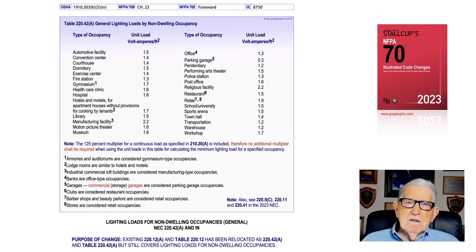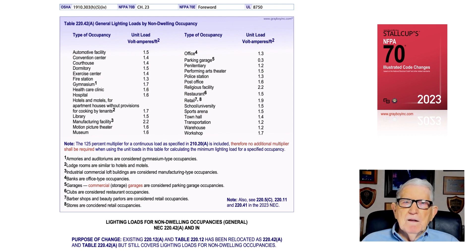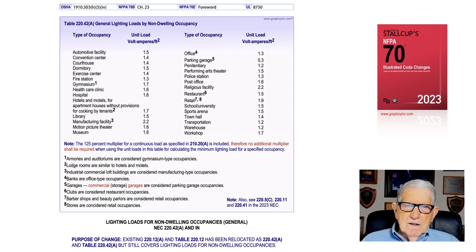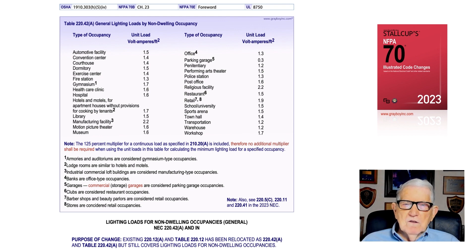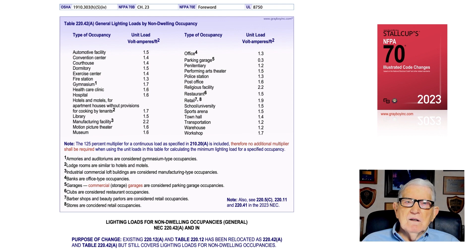If you do not have a listed occupancy in the table, go to table 220.14 and use that section when calculating loads for an unlisted occupancy. The note addresses the 125 percent rule already built into the VA ratings. Note 5 has been revised: commercial storage garages are now considered parking garage-type occupancies. The note also references sections for the dwelling unit, which is no longer listed in table 220.42(a).